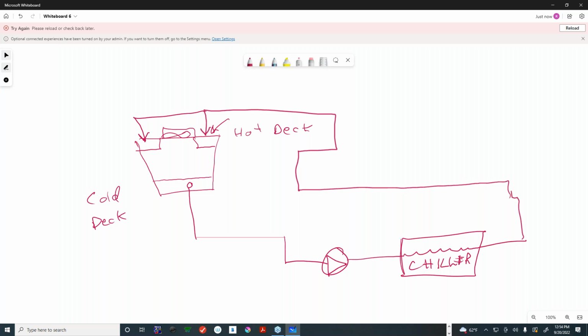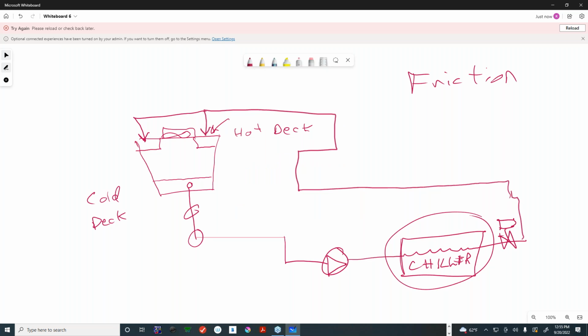Now the pressure drop calculation is done exactly the same way that we did it before. We have the pipe, we have the fittings, we have the equipment, and maybe we have a control valve, or maybe an isolation valve. So I'll stick an isolation valve over here somewhere, and maybe there's a Cv associated with that. So we have pipe, fittings, equipment, control valves, all of that stuff. You do the pressure drop calculation, and that's going to be the friction. I'm going to arbitrarily make up a number, and let's say the pressure drop from my friction calculation comes out to 60 feet.